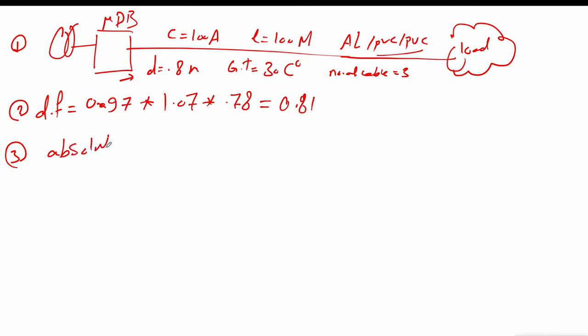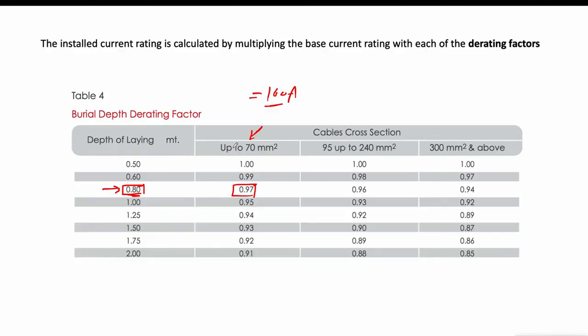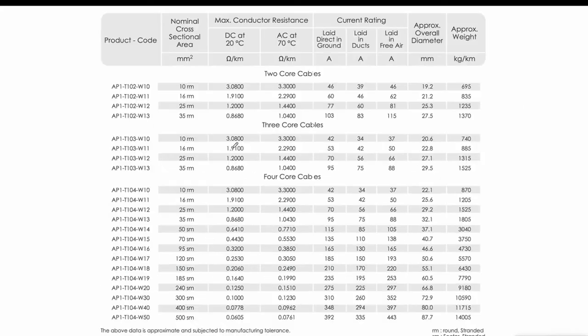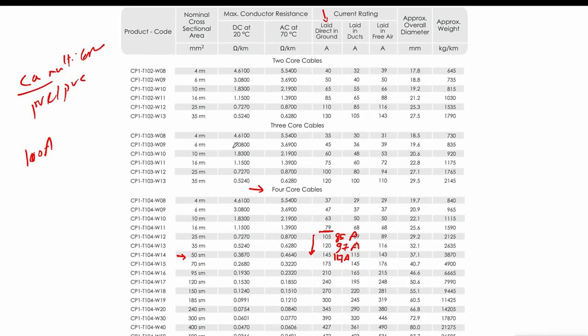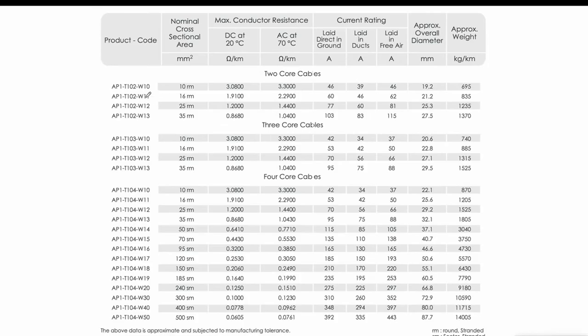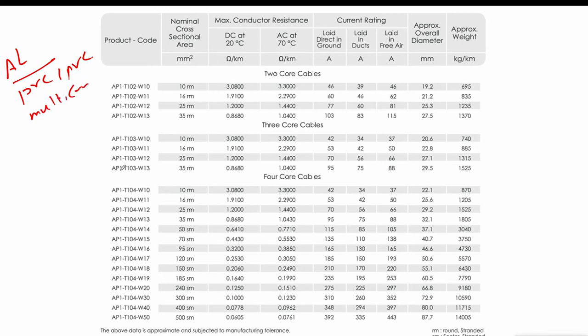Step three: find the absolute current rating. We open the table for aluminum conductors — specifically the aluminum conductor PVC by PVC insulation, multi-core table. We will use a four-core cable and look for the appropriate cross section.